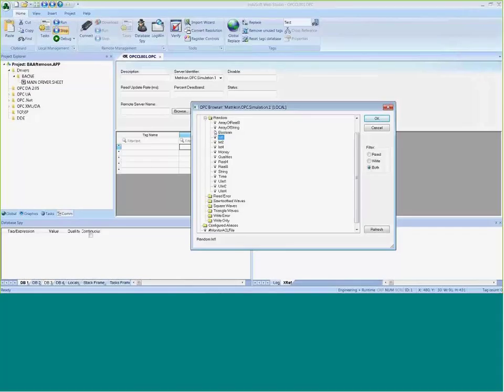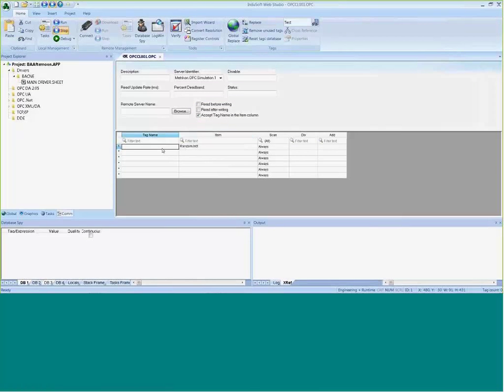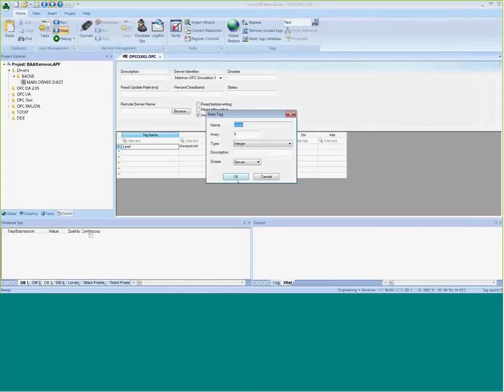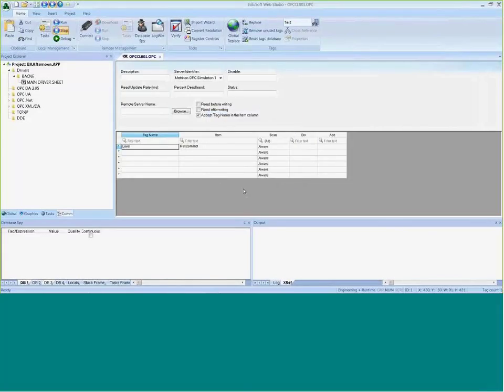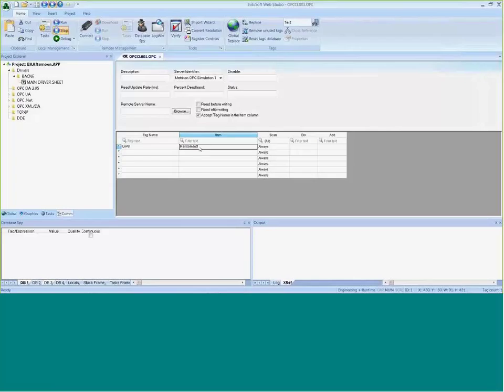The OPC browser content comes from the actual OPC server — InduSoft doesn't configure this. I configured simulation items and chose Integer 1 to represent a level in a tank. I'll tie this to a tag called 'Level' as an integer, and the values will range between 0 and 200. This is where the InduSoft tag gets tied to the item name in the OPC server.